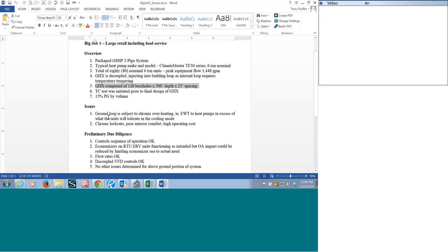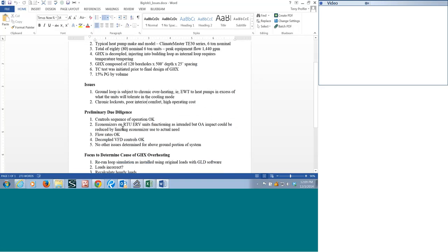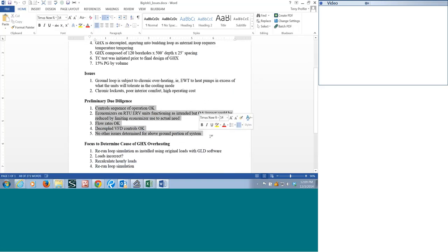So what are the issues? Well, for this example, and we have run into this on various projects, the ground loop was overheating. In other words, the entering water temperature was too warm for the heat pumps to tolerate and still operate in the cooling mode. So we had chronic lockouts, poor interior comfort, and a high operating cost. So if we go through our due diligence, we're assuming we're not seeing any significant issues above ground. Our sequence of operation is assumed to be competent. Flow rates are determined to be okay. We're feeding enough water to the heat pumps. We're not seeing anything that should be harming the operation of the system. So that makes us focus on the ground loop.